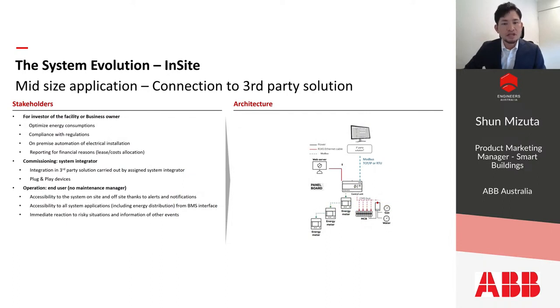Here is one application note of InSite. In this case, we connected multiple third-party Modbus meters to InSite, and this particular case required the InSite to talk to the upstream energy management system, which is also possible through Modbus RTU or Modbus TCP/IP. So InSite was the perfect solution for this particular project.